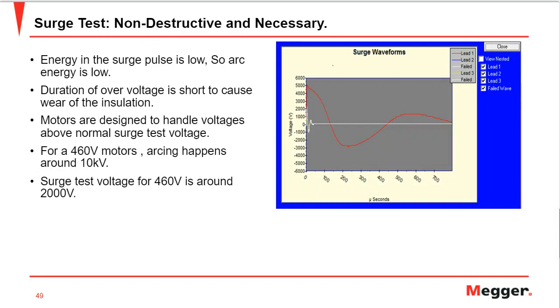And each motor's start and stop effectively is a hipot test and a surge test with an unlimited amount of energy, which can damage the winding. So using a static tester, doing a surge test or a hipot test means we are simulating the same scenario but with low energy and in a precisely controlled manner, which does not harm the insulation of that motor.